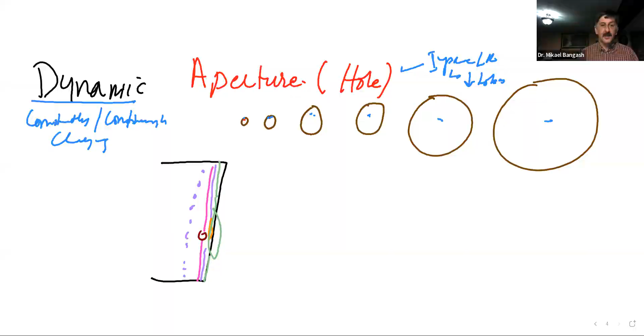If you say that the space between my fingers makes an aperture, that goes like this. But the whole purpose of it was mainly to improve the lateral resolution of the beam, mainly by enabling the beam to focus at multiple points. And the other side is also to reduce the production of lobes. So from time to time, a greater or smaller number of PZTs partake in the formation of your beam.